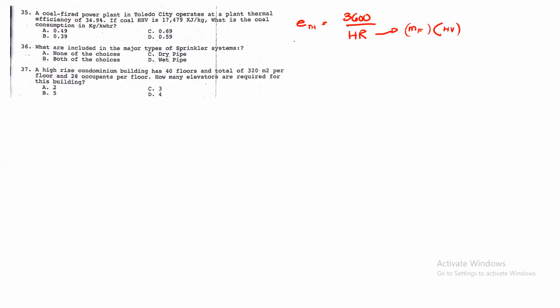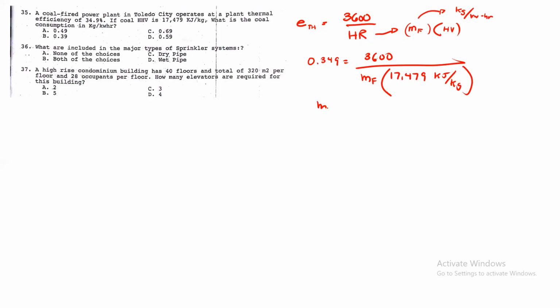So, substitute lang to. Ilan yung thermal efficiency natin? 34.9%. So, 0.349 is equals to 3,600 divided by mass ng fuel times heating value na 17,479 kilojoules per kilogram. Tatandaan nyo, ang unit dito ng mass ng fuel kapag heat rate is kilograms per kilowatt hour. Makuha natin mass ng fuel dito is equal to, ilan lalabas dito? 0.59 kilograms per kilowatt hour.